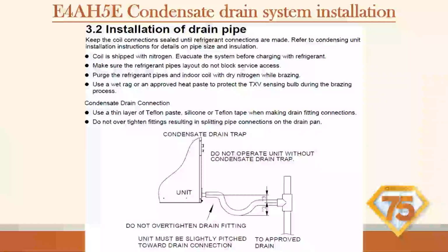This is important. Hopefully we're all using P-traps. I've seen some pretty minimal P-traps, but this is a P-trap. I know we sell them pre-made. You can make your own. I've seen some traps though where they are about equal. We need to have the point where it's lower so the water can drain, but we have water standing in there. So this is a negative pressure cabinet, or else it would pull the air back in and not drain correctly. So this allows the water to drain smoothly.